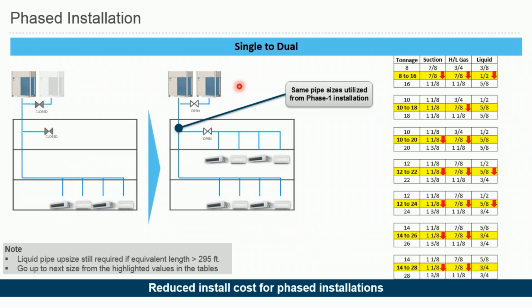Then the next tenant starts moving into the building, which means you need more indoor units for that new tenant. Now it's time to add these new indoor units, and you open this valve, which probably means you will need more capacity out of your outdoor unit system. That's when you add this additional condensing unit, increasing your total system capacity by opening this valve and adding that new outdoor unit. And you're doing this without changing your main pipeline sizes. Whatever main pipeline sizes you use in the first phase of the project, you will not need to make any changes there in the second stage, or depending on how many stages you have in your project.